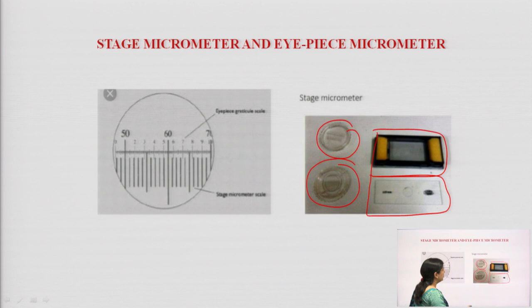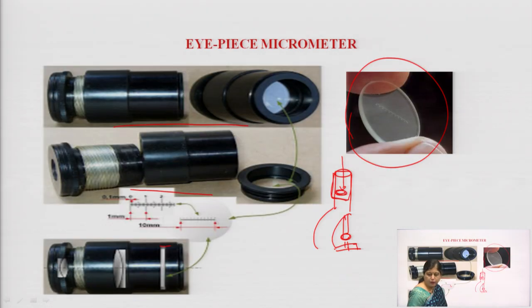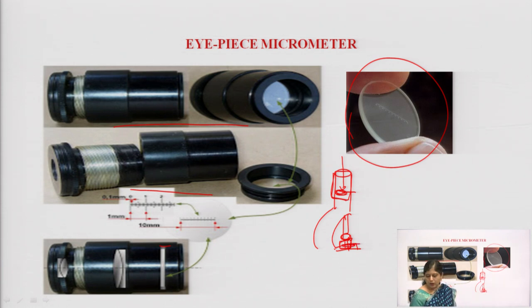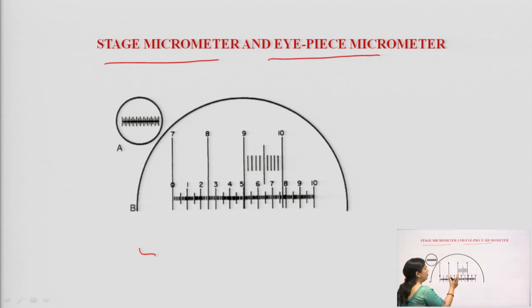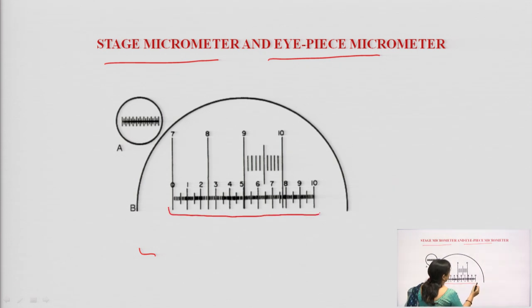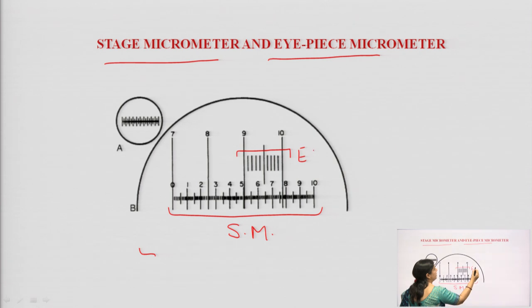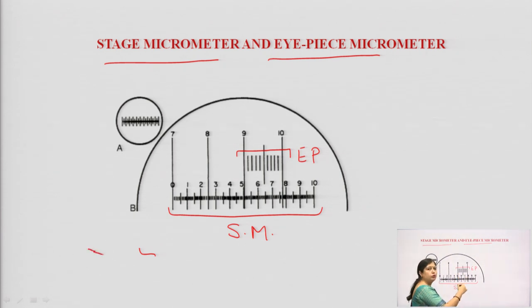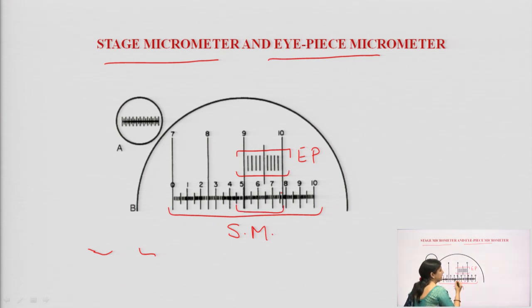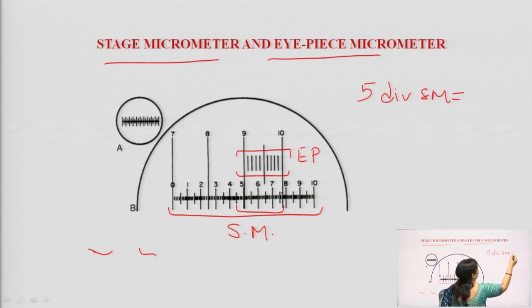After placing the eyepiece micrometer, we also use the stage micrometer, placed just below the objective lens. Both have their own scales and measurements. We superimpose these two scales and do the calibration by counting the number of divisions of the eyepiece micrometer matching with the stage micrometer. For example, if five divisions of the stage micrometer coincide with seven divisions of the eyepiece micrometer, we have that relationship.